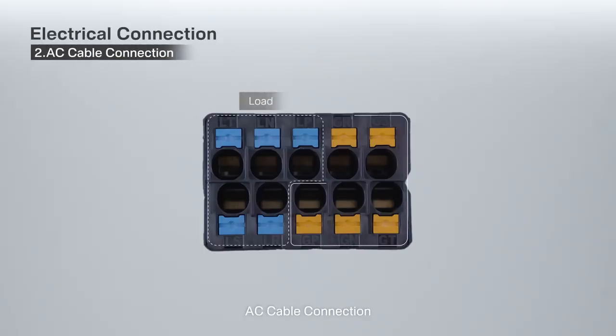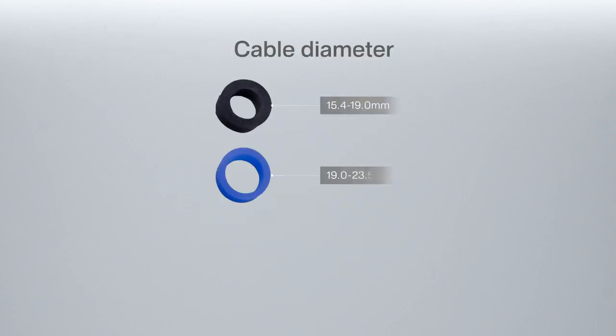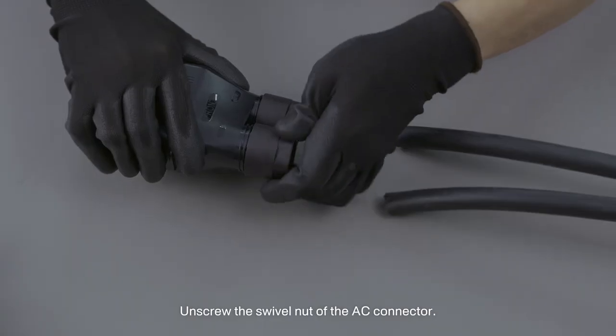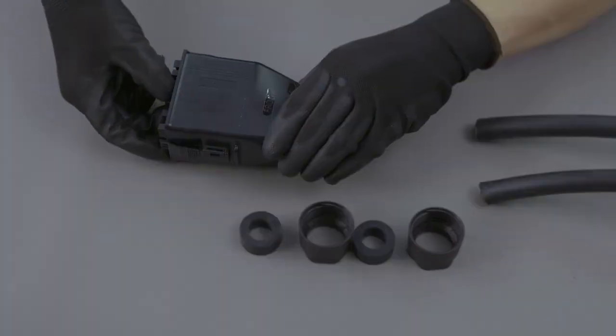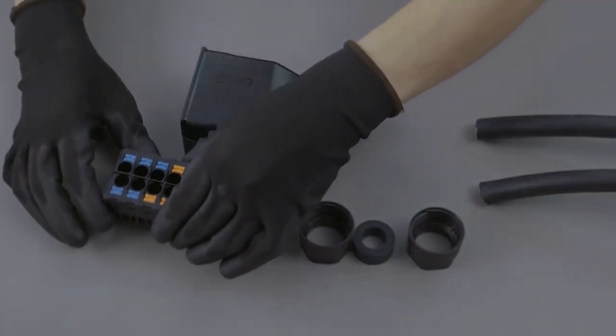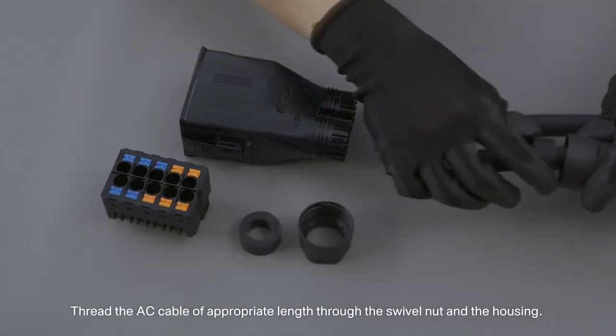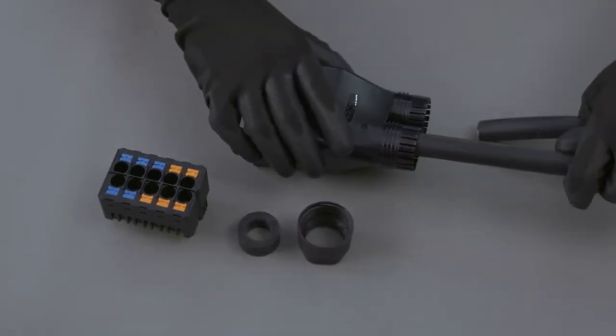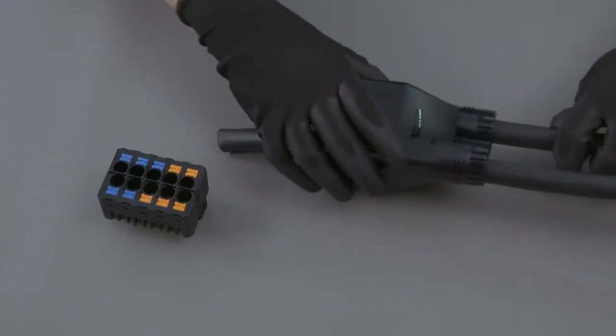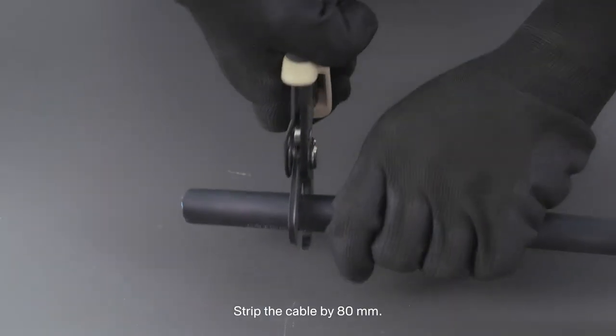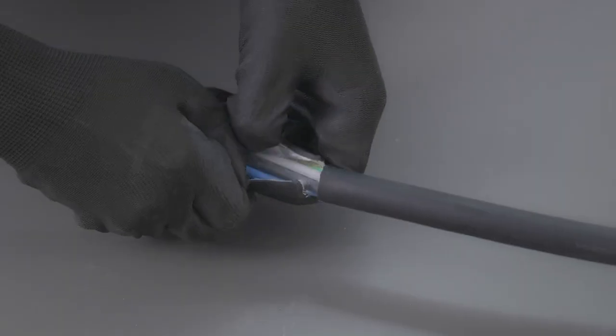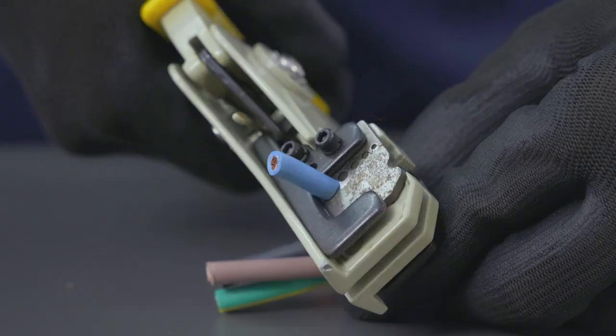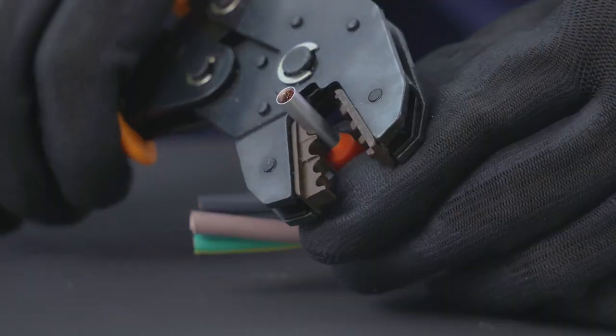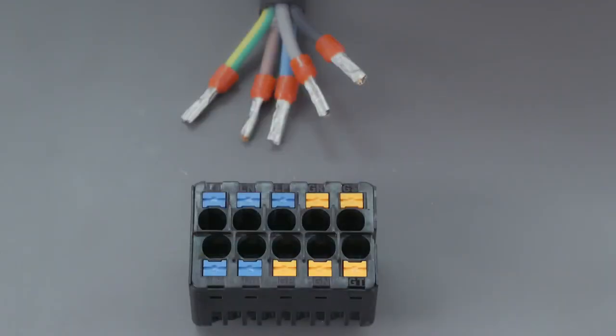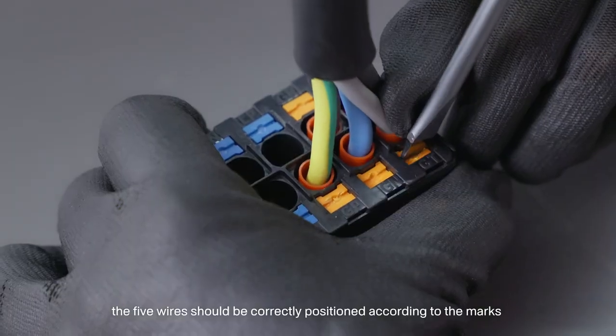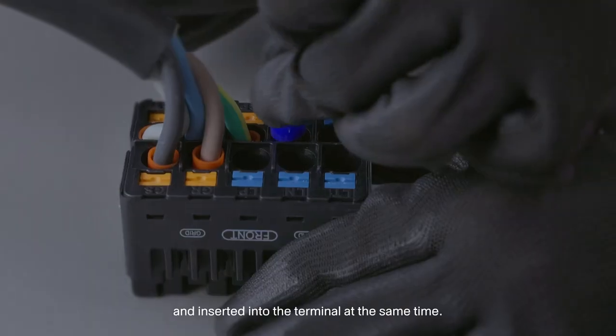2. AC cable connection. Unscrew the swivel nut of the AC connector. Take out the terminal plug from the housing. Thread the AC cable of appropriate length through the swivel nut and the housing. Strip the cable by 80 millimeters. When wiring, the 5 wires should be correctly positioned according to the marks and inserted into the terminal at the same time.